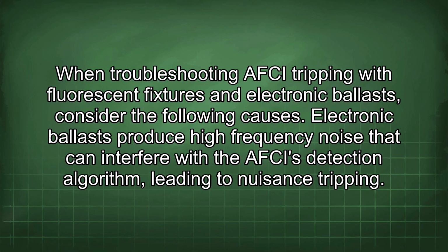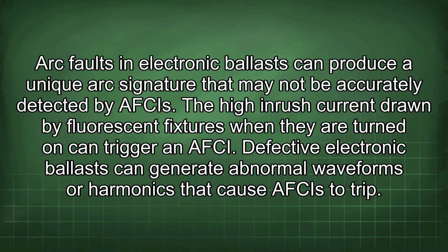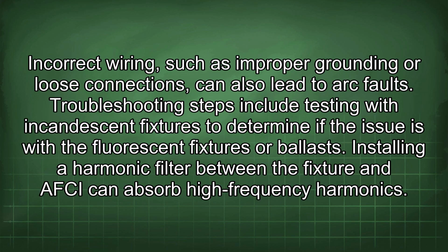When troubleshooting AFCI tripping with fluorescent fixtures and electronic ballasts, consider the following causes. Electronic ballasts produce high-frequency noise that can interfere with the AFCI's detection algorithm, leading to nuisance tripping. Arc faults in electronic ballasts can produce a unique arc signature that may not be accurately detected by AFCIs. The high inrush current drawn by fluorescent fixtures when they are turned on can trigger an AFCI. Defective electronic ballasts can generate abnormal waveforms or harmonics that cause AFCIs to trip. Incorrect wiring, such as improper grounding or loose connections, can also lead to arc faults.